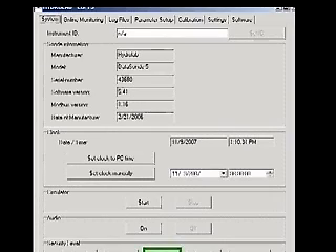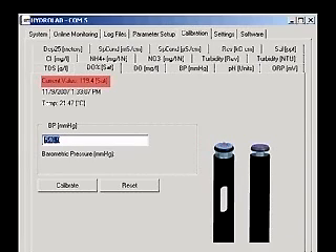Establish a connection with the Sonde with Hydras 3LT. Click the button labeled Operate Sonde. When the Sonde finishes its initialization, click the Calibration tab, then click the D-O percent SAT tab. You will see a picture of the Clark cell probe, the current dissolved oxygen reading, the date and time, and the current temperature.